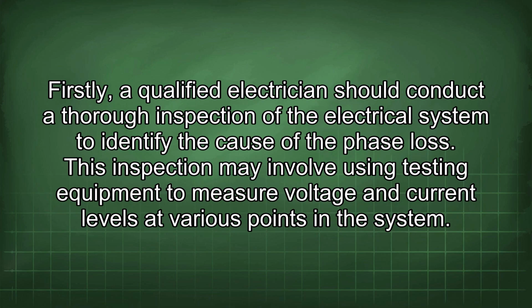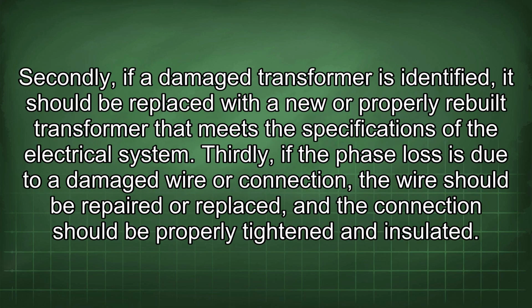Firstly, a qualified electrician should conduct a thorough inspection of the electrical system to identify the cause of the phase loss. This inspection may involve using testing equipment to measure voltage and current levels at various points in the system. Secondly, if a damaged transformer is identified, it should be replaced with a new or properly rebuilt transformer that meets the specifications of the electrical system. Thirdly, if the phase loss is due to a damaged wire or connection, the wire should be repaired or replaced, and the connection should be properly tightened and insulated.